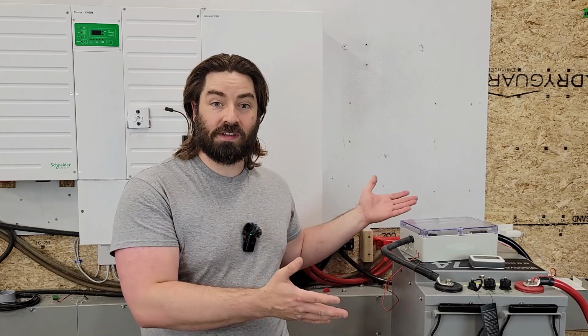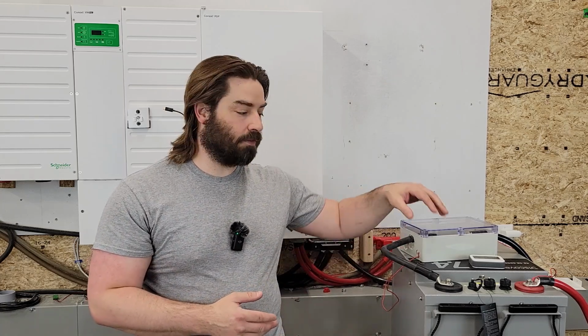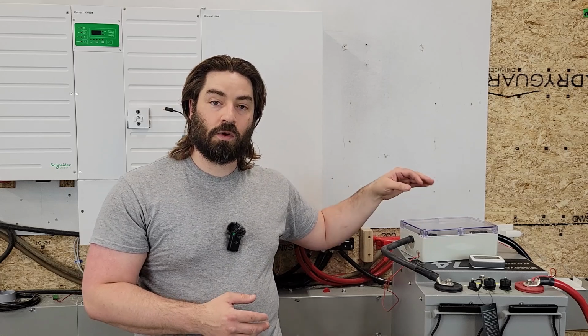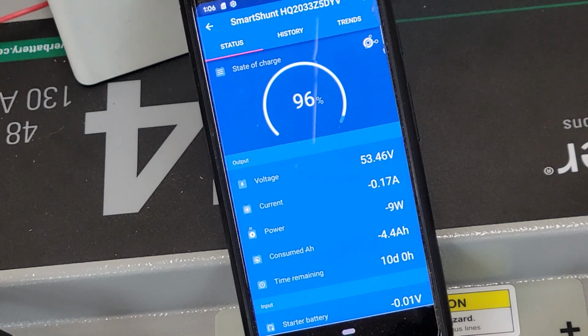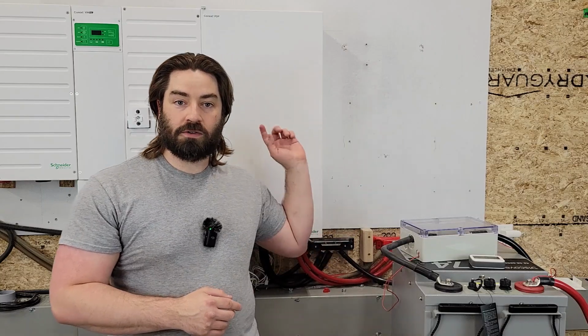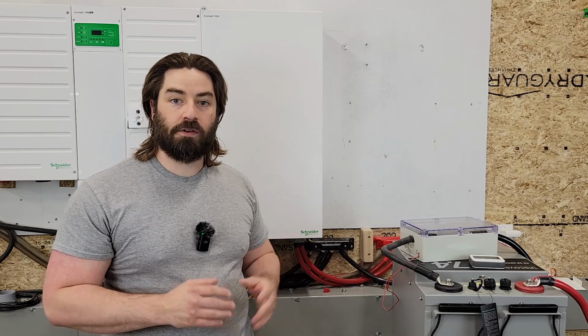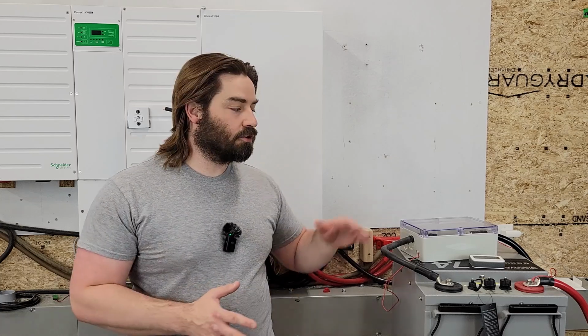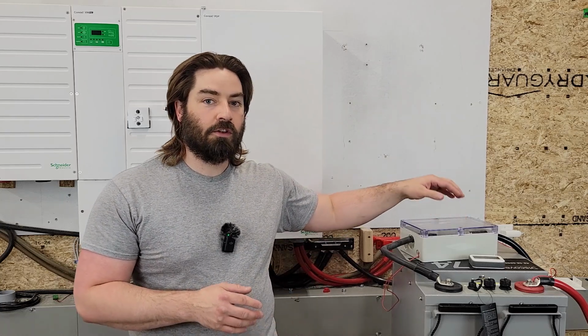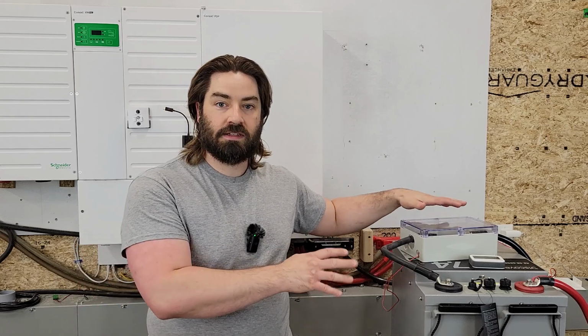That should take about an hour to discharge, and I've got the whole test set up. We've got some 4-aught wire going from the battery to the Victron shunt. We're going to monitor what the Victron shunt is doing through the Bluetooth app on this old cell phone. That 4-aught wire goes into the Schneider PDP, or power distribution panel, which is powering this Schneider inverter. I have just one Schneider inverter connected right now, and we're going to turn on as many space heaters as required to try to get as close as possible to 130 amps on the DC side.